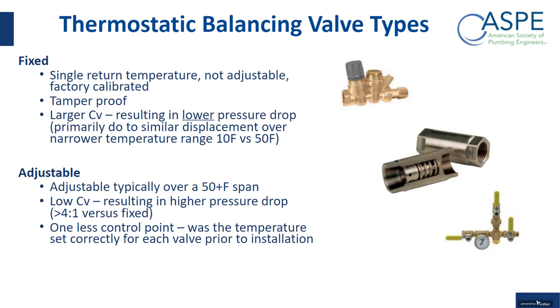These typically have a larger CV than the adjustables because they're going from fully extended to fully retracted over 10 degrees Fahrenheit, where the adjustables are generally designed with a much larger temperature span, on the order of 50 degrees Fahrenheit. So you're getting a similar motion over 50 degrees that you were getting over 10 degrees with the fixed. The adjustables tend to have a lot lower CV at the design point, which can produce a much higher pressure drop. You just have to take that into account when you're sizing the head pressure of your pump.